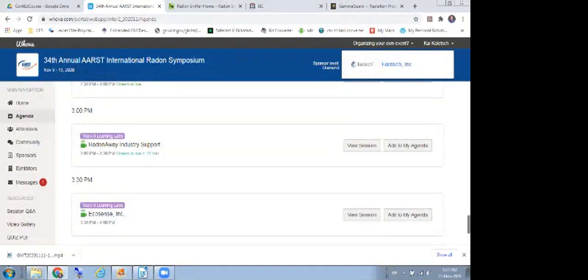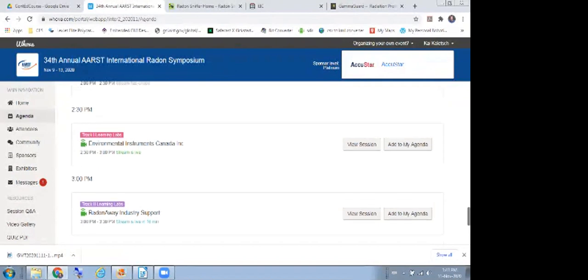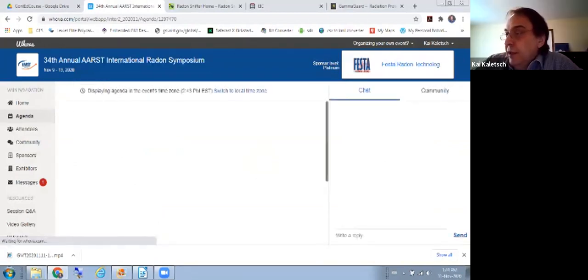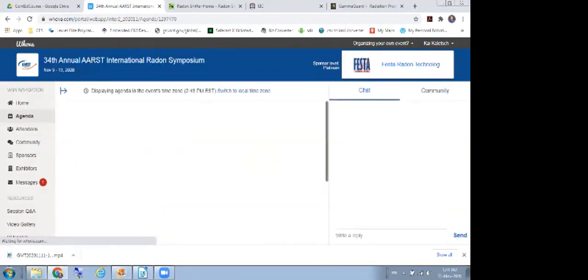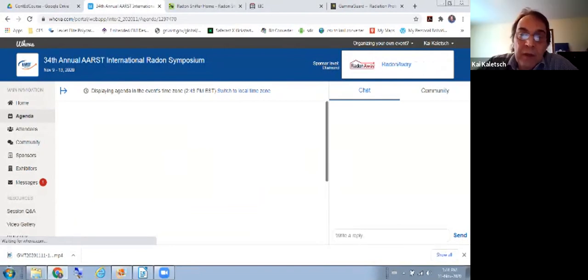Okay. I guess my last question would be, obviously with a lot of high radon, do you have any kind of background buildup inside the unit, or do you have to flush it, say, if you were going to another area? So yeah, in real time, the algorithm will try and subtract the background. So that's from between one reading and the next.